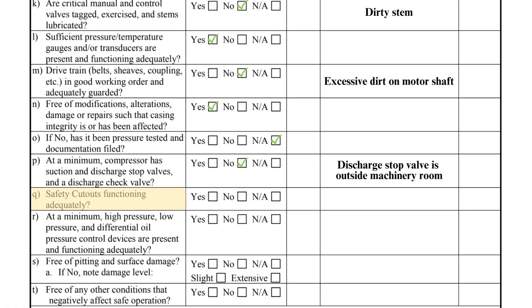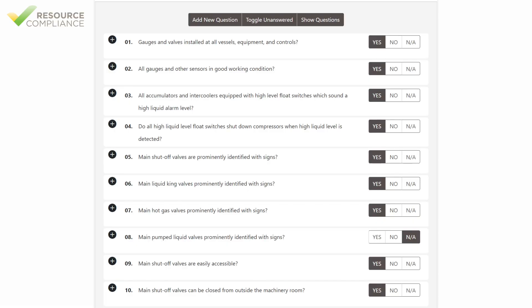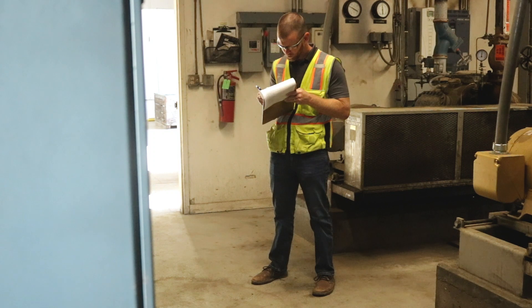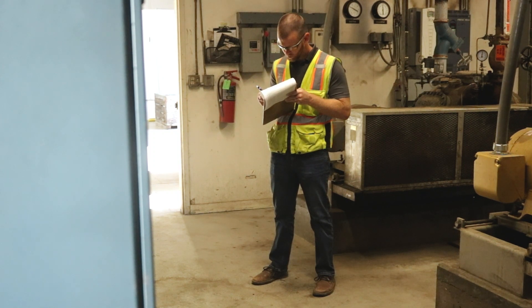Item Q inquires if the safety cutouts are functioning properly. These can be tested during the inspection, or documentation of the tests can be reviewed. Item R builds on the previous question by asking if at minimum the high pressure, low pressure, and differential oil pressure control devices are present and functioning adequately. While many compressors have numerous cutouts, these are often deemed most important, hence a question specifically about them.